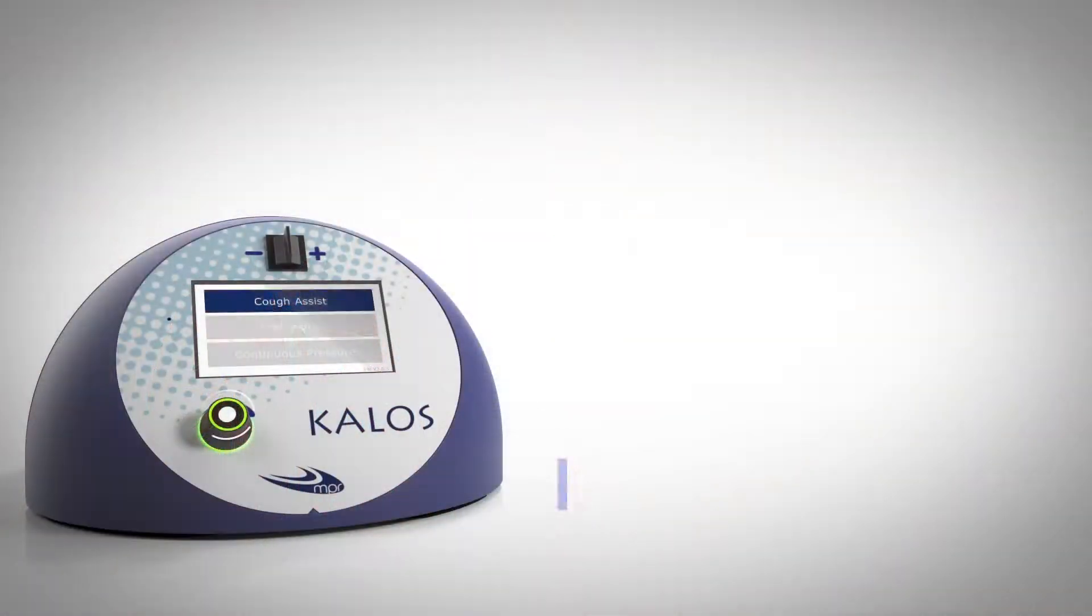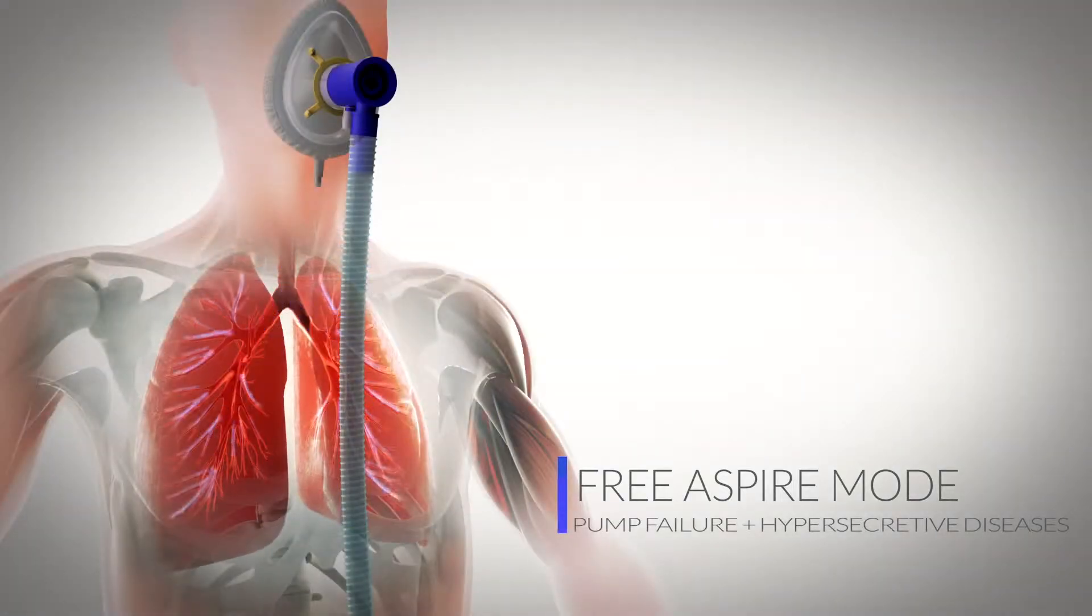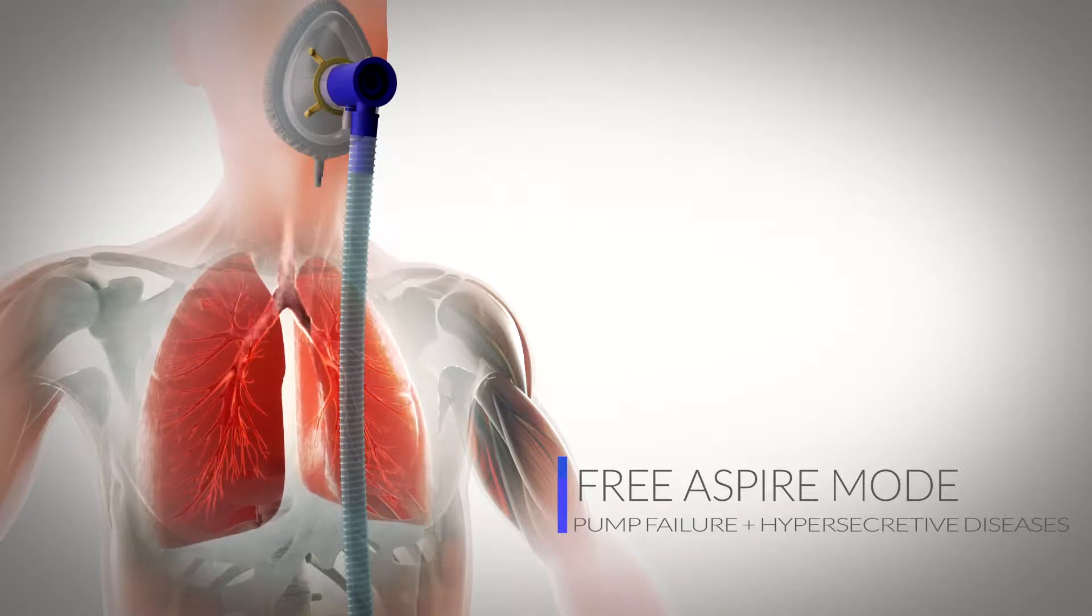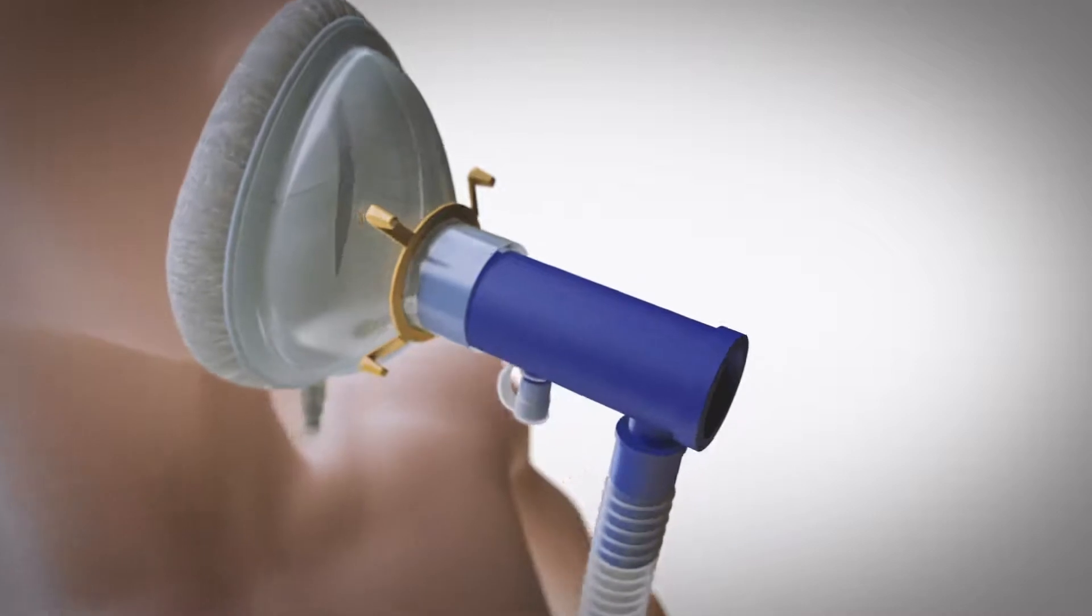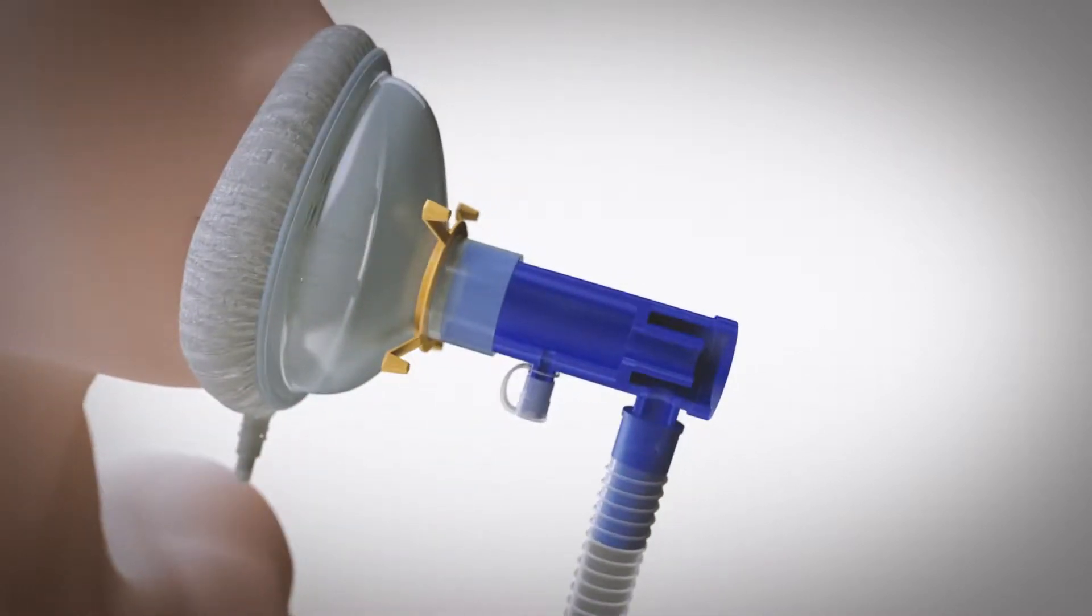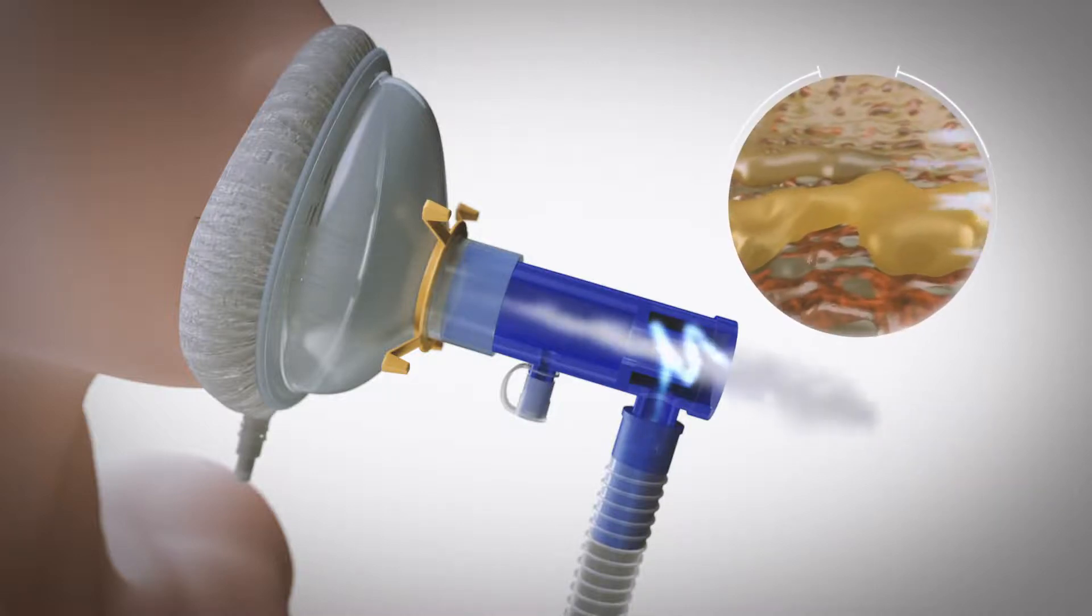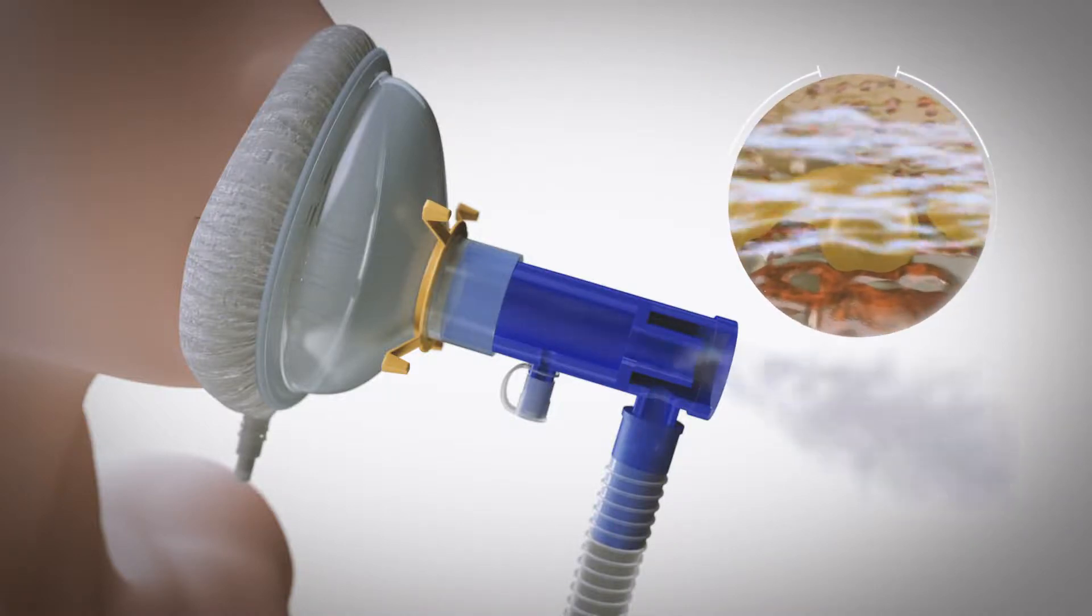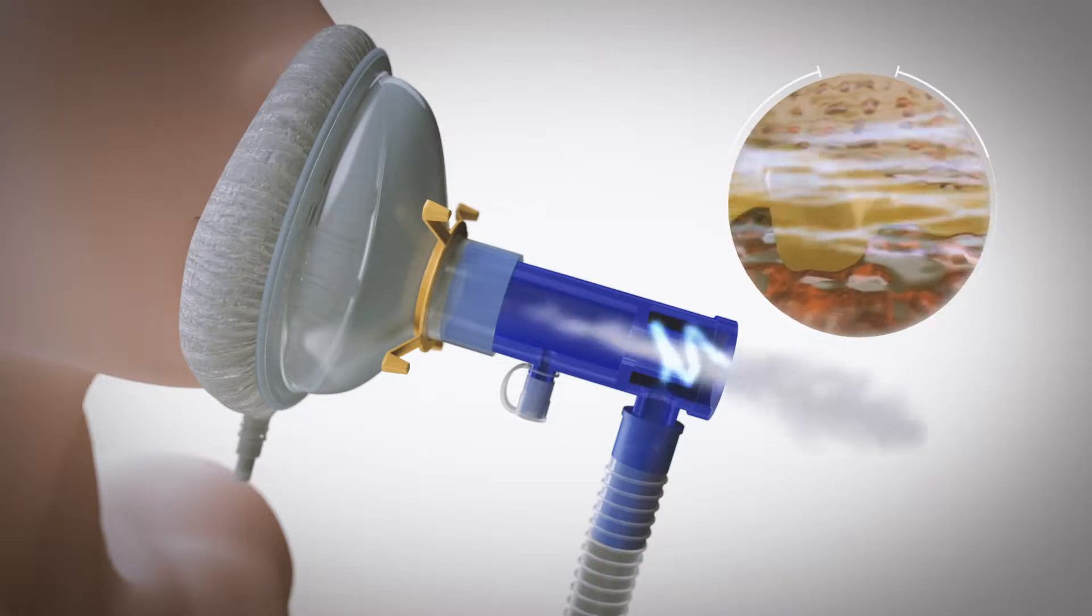In the free aspire mode, the EFA technology uses a patented connection to accelerate the exhaled tidal flow, promoting gentle mobilization of secretions from the middle to the upper airways. A turbulent flow is generated inside the connection and when this flow meets the flow exhaled by the patient, the latter is accelerated and drawn out. No negative pressure is created in the airways.